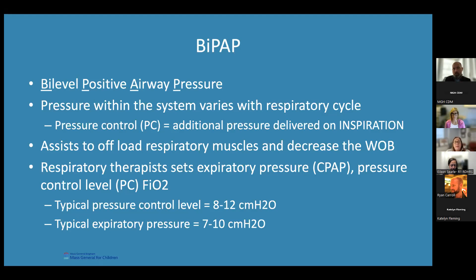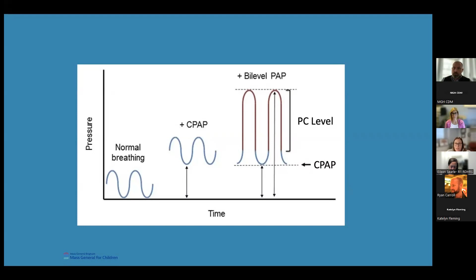This is just a pictorial representation of what this actually looks like. You see the normal breathing on the far left-hand side, where as the curve goes up, that's inspiration, and then on the downward slope, that's exhalation. The pressure with normal spontaneous breathing gets to about 0 at the end of exhalation. For CPAP, we have the same delta, the same size of breath, but we're just raising that expiratory pressure off of 0 to something like 7 or 8 or 9 to assist the patient to avoid that premature alveolar and airway closure. In BiPAP, or bi-level positive airway pressure, we still see that same CPAP level where the whole graph is raised off of the baseline of 0, but then we're adding additional pressure on inspiration to make that change in the volume of air that's moving in and out of the lungs greater to unload those respiratory muscles and hopefully clear some CO2.